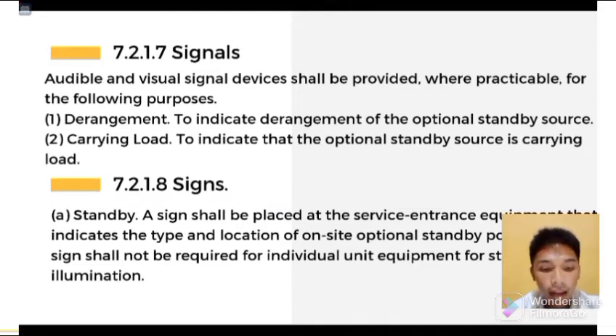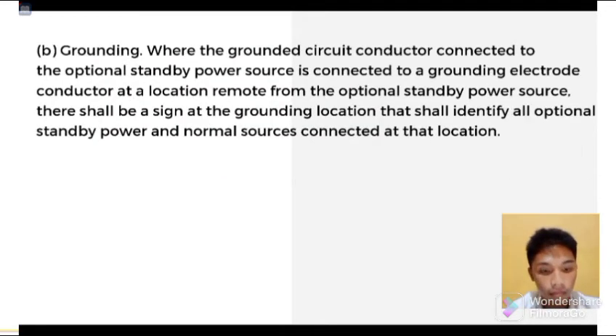For the signs, a sign shall be placed at the service entrance equipment that indicates the type and the location of on-site optional standby power sources. A sign shall not be required for individual unit equipment for standby illumination. Grounding. Where the grounded circuit conductor connected to the optional standby power source is connected to a grounding electrode conductor at a location remote from the optional standby power source, there shall be a sign at the grounding location that shall identify all the optional standby power source and the normal sources connected at that location.